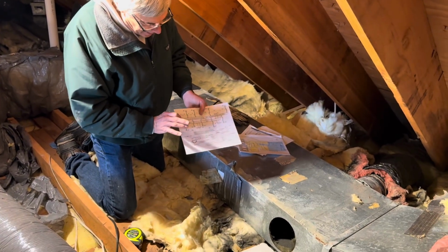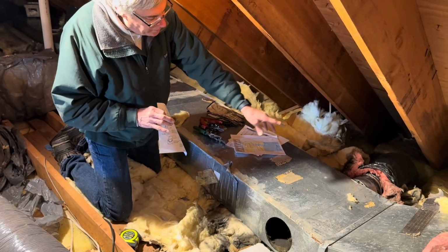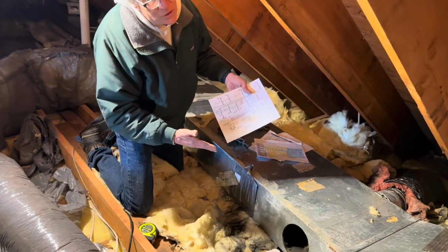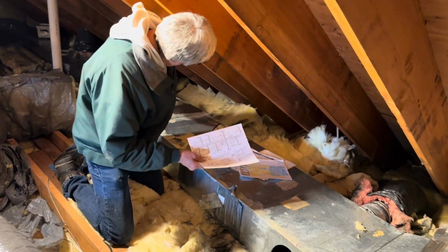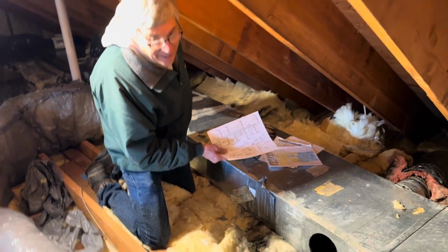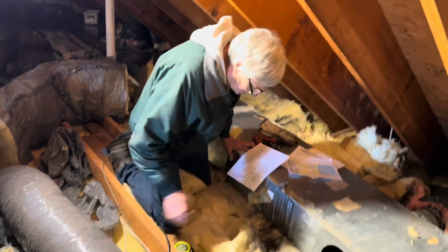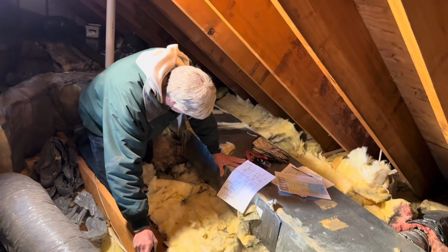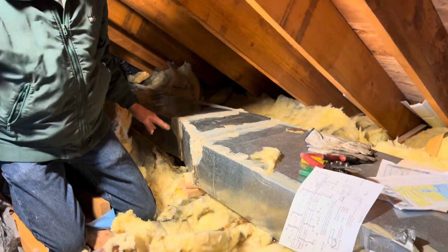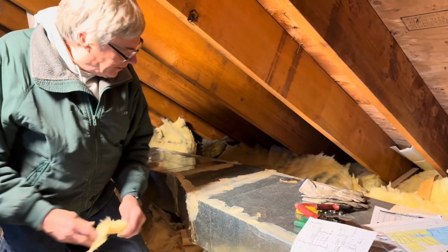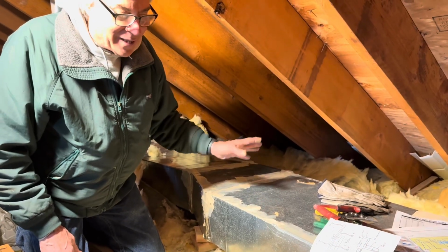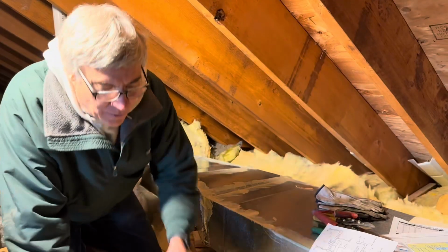So now we're going to take 1, 2, 3 off of the larger size duct, and that reduces the total available amount of air to the rest of the duct. And that total amount of volume of air needs to get a smaller duct size. That duct size is going to go through what's called a transition.